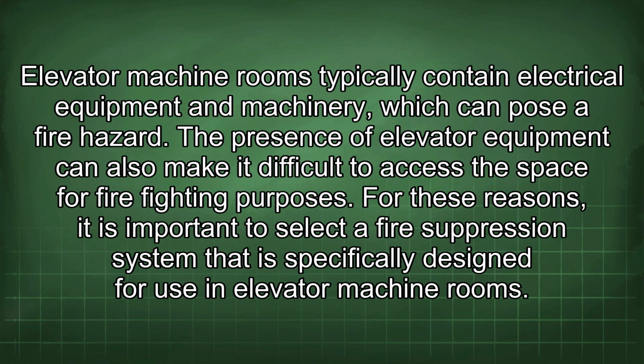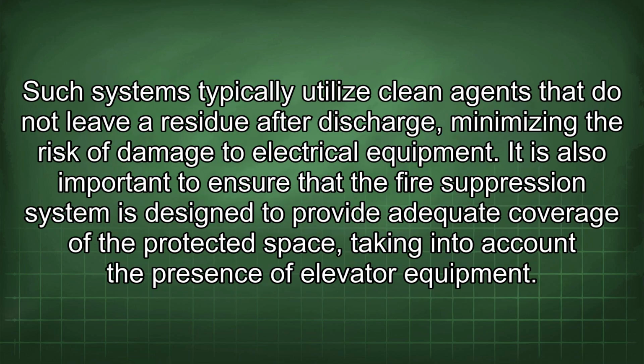Elevator machine rooms typically contain electrical equipment and machinery which can pose a fire hazard. The presence of elevator equipment can also make it difficult to access the space for firefighting purposes. For these reasons, it is important to select a fire suppression system that is specifically designed for use in elevator machine rooms. Such systems typically utilize clean agents that do not leave a residue after discharge, minimizing the risk of damage to electrical equipment. It is also important to ensure that the fire suppression system is designed to provide adequate coverage of the protected space, taking into account the presence of elevator equipment.